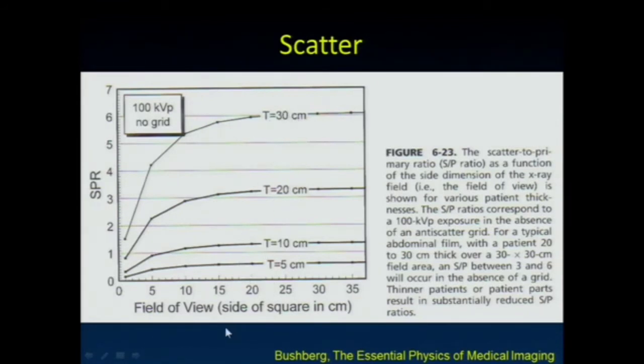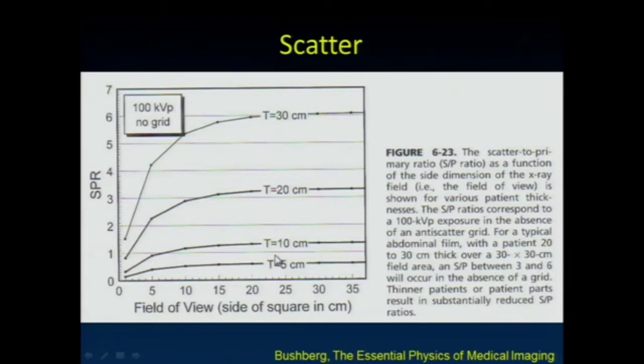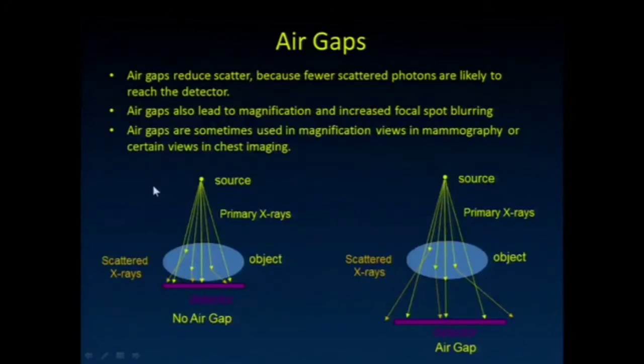They opened the field of view to different sizes and measured the scatter-to-primary ratio. With a very small five-centimeter phantom, even as the field of view got bigger there wasn't a lot of scatter—so for pediatric patients and small parts, scatter is not a huge issue. For larger patients, getting the field of view as small as possible becomes very important to keep the scatter-to-primary ratio down.